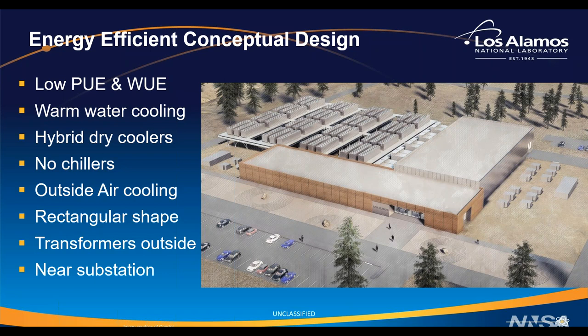Most of the heat is rejected with the hybrid dry coolers and the warm water cooling, but there's still a small amount of heat that comes out of the cabinets, and when you're looking at a 40 megawatt data center that adds up. So you still have to have some airflow through your data center, and we use outside air cooling for that. The rectangular shape provides a longer wall to allow enough air into the facility, as well as shortening the distance to the outside transformers on the right side.